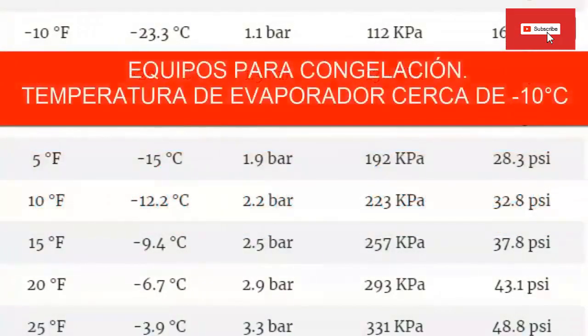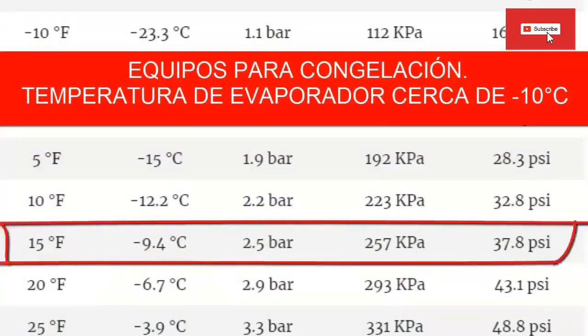For an average temperature system, freezing to minus 9.4 degrees Celsius (about 15 degrees Fahrenheit), we need a pressure on the low manometer of approximately 37.8 psi, equivalent to 2.5 bars.